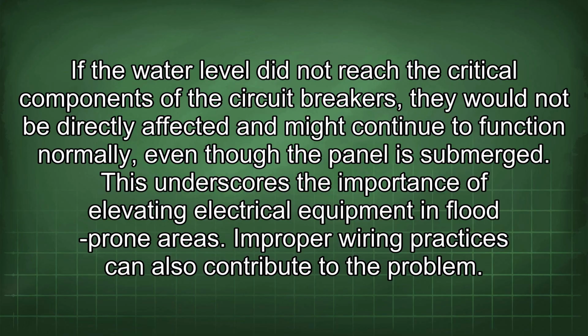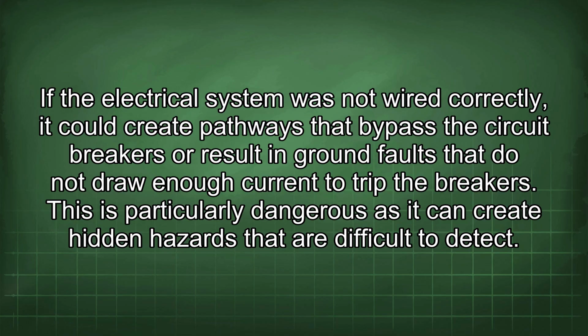Improper wiring practices can also contribute to the problem. If the electrical system was not wired correctly, it could create pathways that bypass the circuit breakers or result in ground faults that do not draw enough current to trip the breakers. This is particularly dangerous as it can create hidden hazards that are difficult to detect.